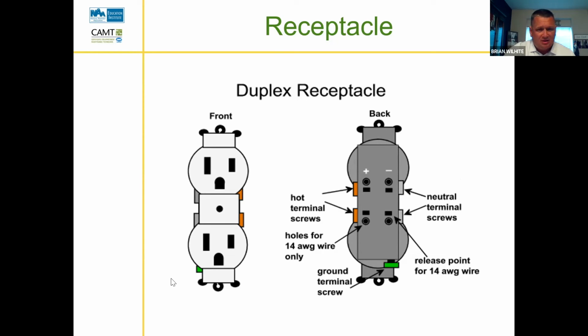Have you had any issues with that, Candace, on your new properties? Some, a little bit, where they do pop out, or just the opposite, where when you go to release them, it's very difficult to get the wire out without cutting it off. Yeah, correct. And so I'm old. I don't want to say I'm old school because it makes me feel old, and I'm not really all that old yet. But I really like the connections on the screws. One, I can determine how my wire sets by looping it in the direction of tightening, and I actually pinch mine a little bit around that screw, so I'm making a good connection. I know by tightening that screw that I'm getting a good solid connection to that wire. And if I ever have to release it, I can undo the screw very easily. So if you ever have the option to choose between the two, please defer to the screw side and hook the wire up that way rather than the plug-in terminal.